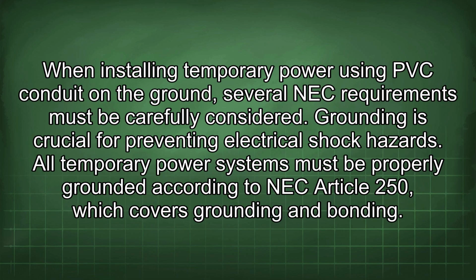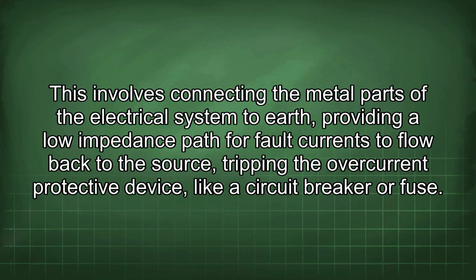When installing temporary power using PVC conduit in the ground, several NEC requirements must be carefully considered. Grounding is crucial for preventing electrical shock hazards. All temporary power systems must be properly grounded according to NEC Article 250, which covers grounding and bonding. This involves connecting the metal parts of the electrical system to earth, providing a low impedance path for fault currents to flow back to the source, tripping the overcurrent protective device, like a circuit breaker or fuse.